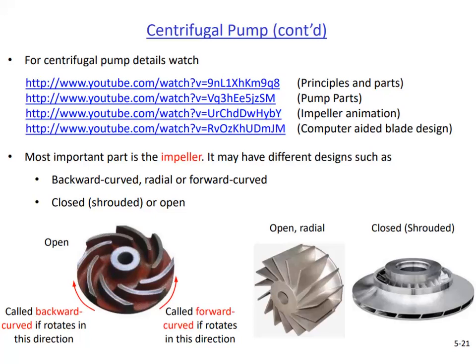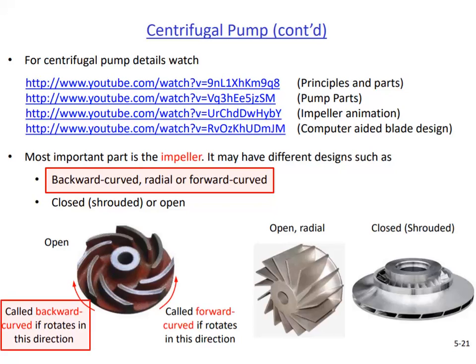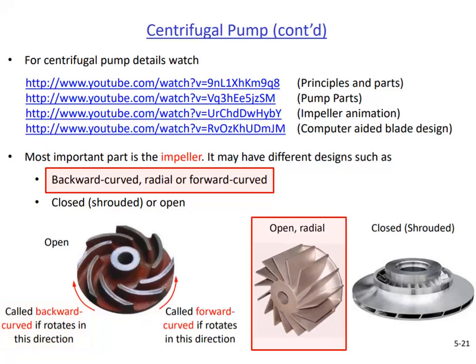The pump shown in the previous slide had backward curved blades. Blades are called backward curved, radial, or forward curved, based on their curvature with respect to the rotation direction. The most common type is backward curved, where the blades are curved opposite to the flow direction. If the blades are straight with no curvature, they are called radial blades.